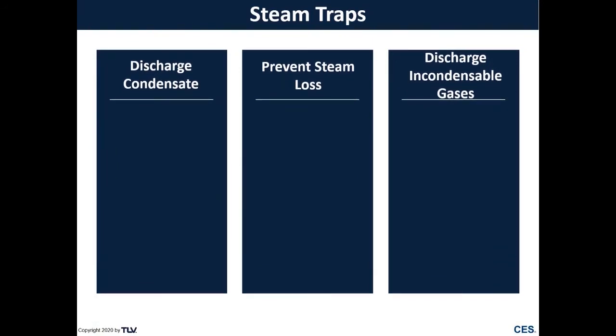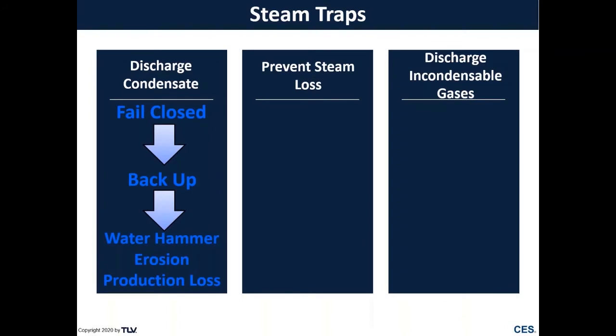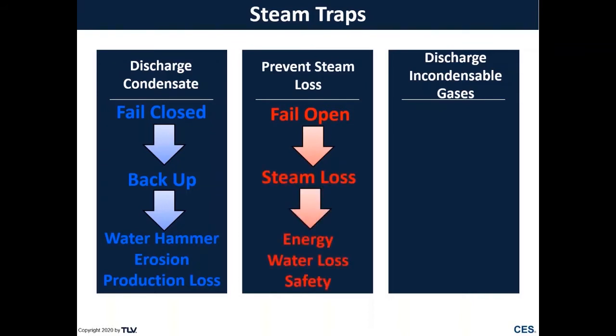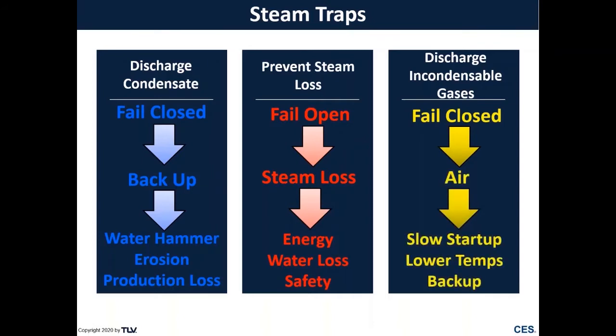What happens when a steam trap fails? If the steam trap fails closed, we back up condensate, leading to water hammer, erosion, and production losses. If the trap fails open, we have steam loss — wasted energy, lost water, and a potential safety situation if discharging to atmosphere. We may also have problems with the trap failing closed due to non-condensible gases like air, causing slower startup, lower temperatures, condensate backup, water hammer, and production losses.